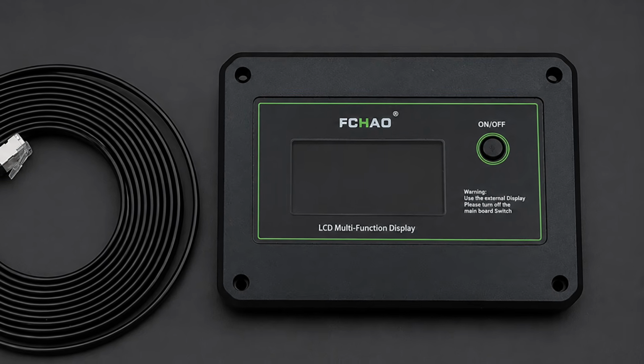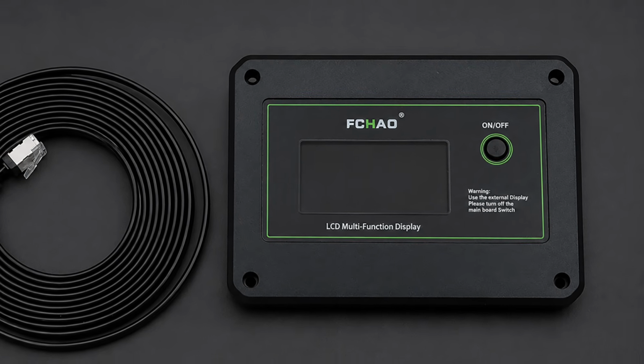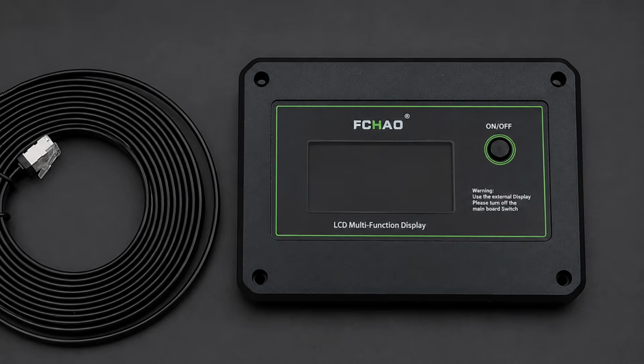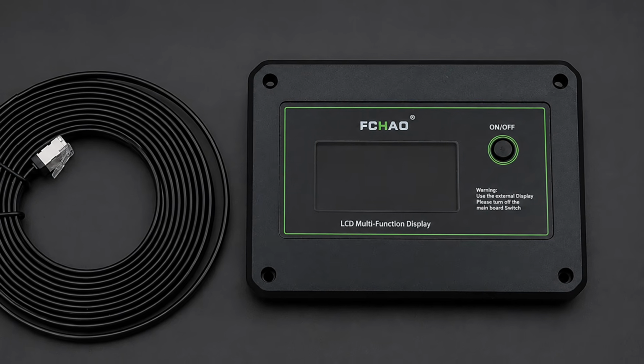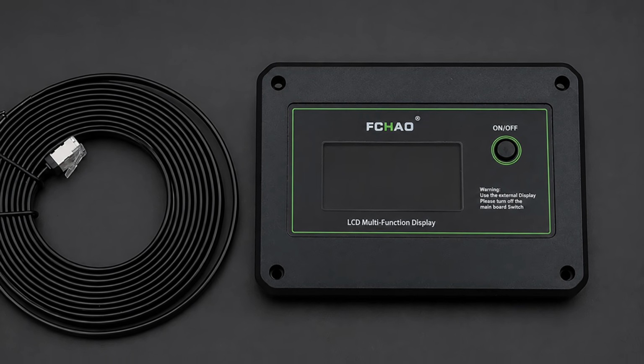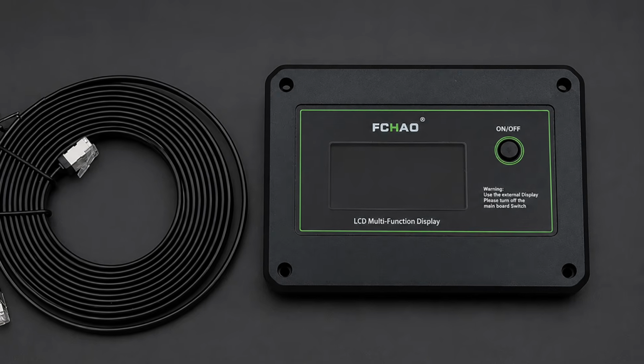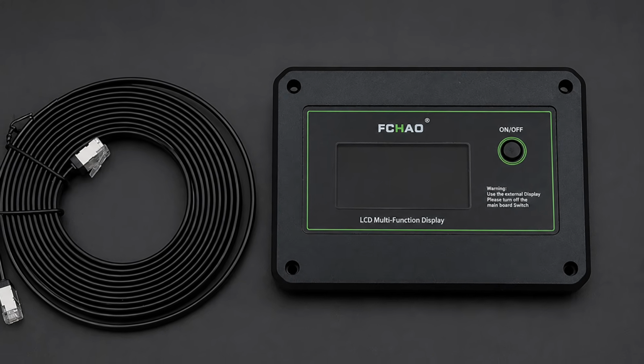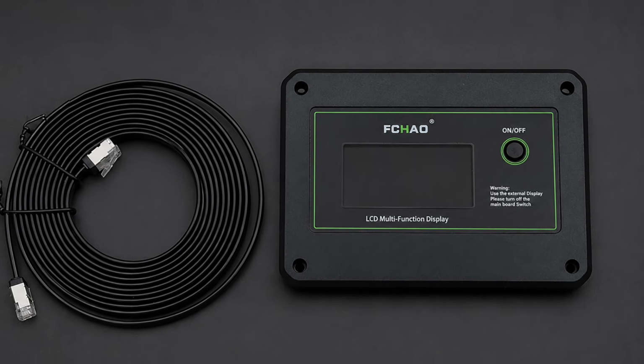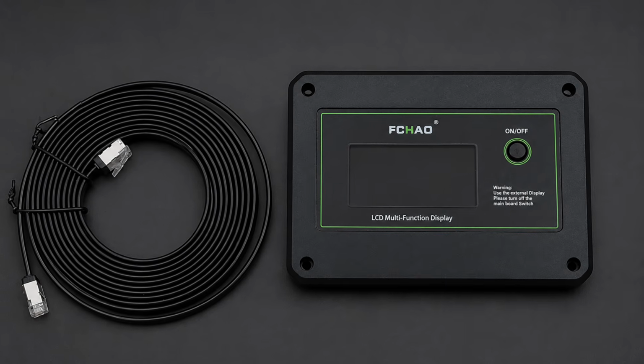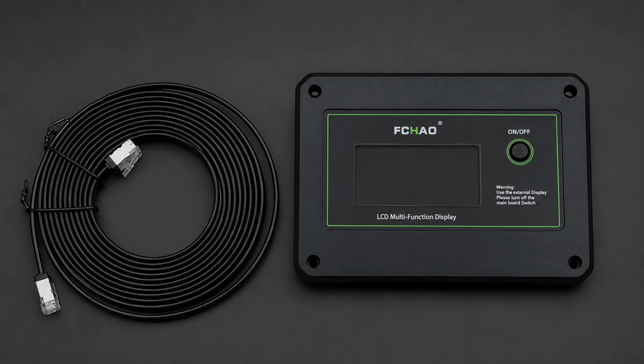There is a warning on the display housing: when using the external display, the main switch on the inverter itself must be turned off. That is, control in this case is transferred here to the remote module. For stationary installation, this is a convenient solution, as there is no need to reach the inverter itself every time to check parameters or turn the device on.